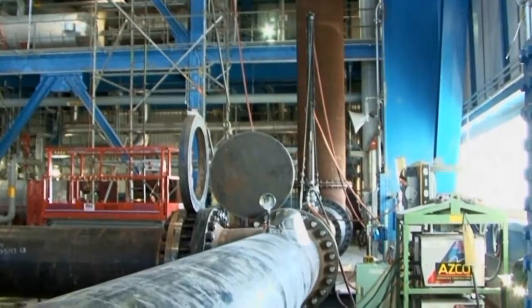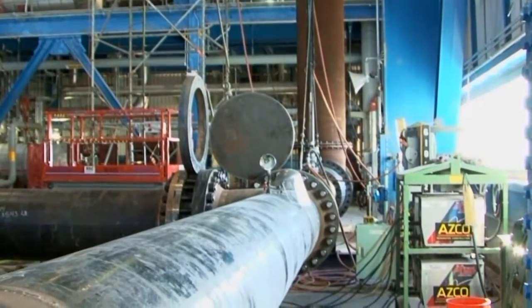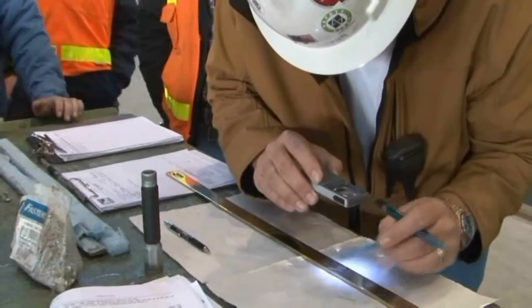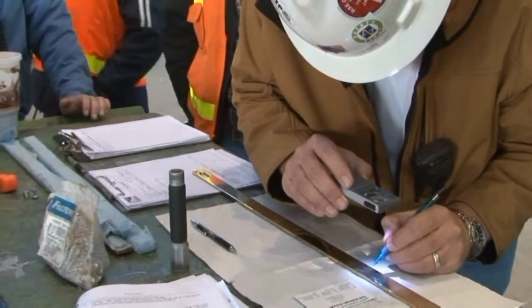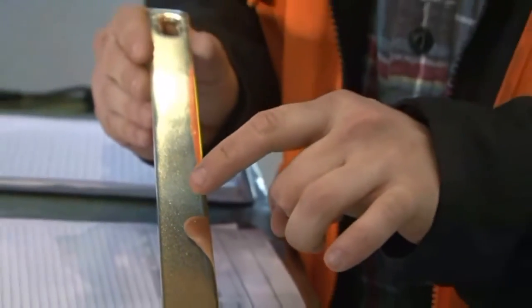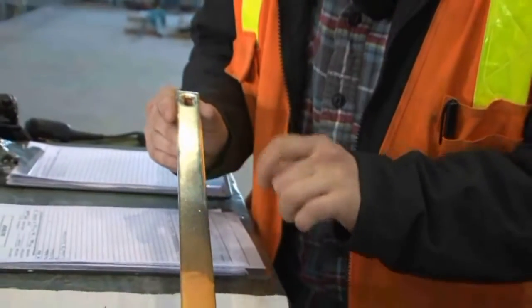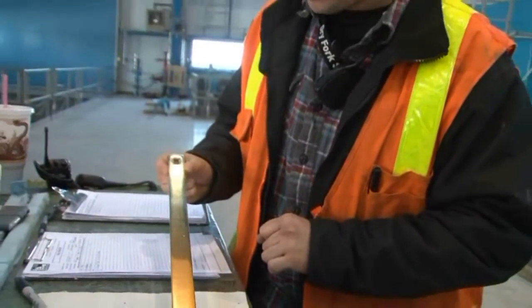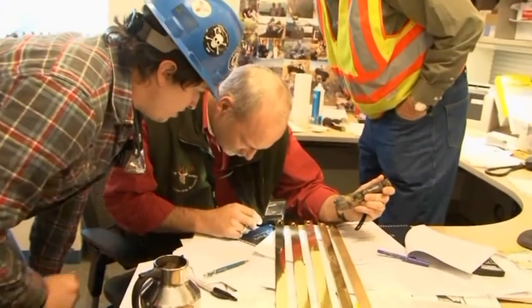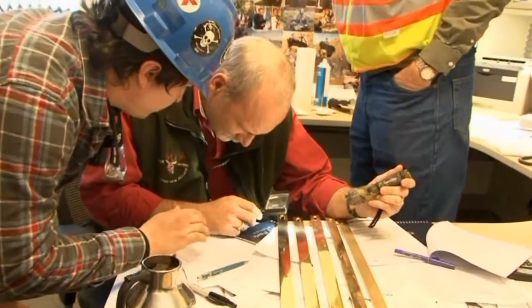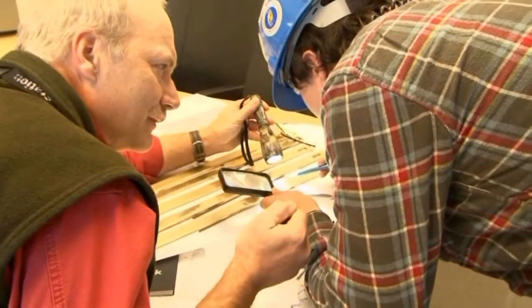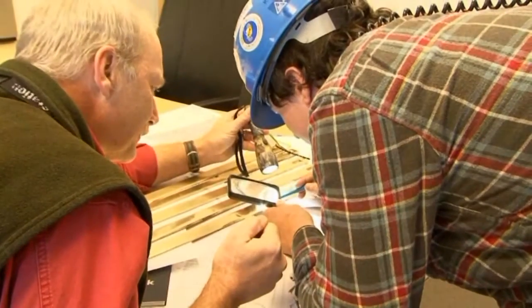The target will show damage from debris flying through the pipes. On this day, blow number 100 gets target tested. You cannot have more than one impact within 1 square inch on the target. The air blows will continue for another 12 hours before a target is tested again. I mean, it didn't penetrate it. You see what I'm saying?